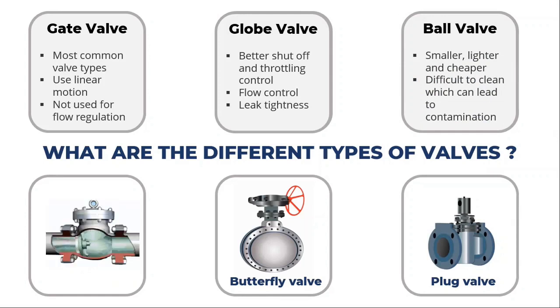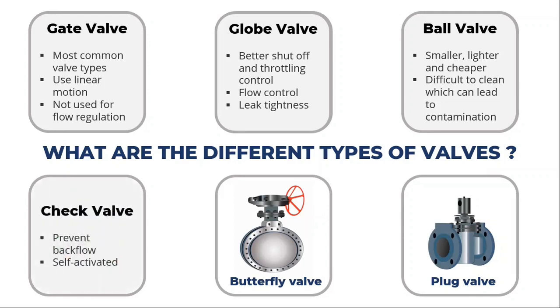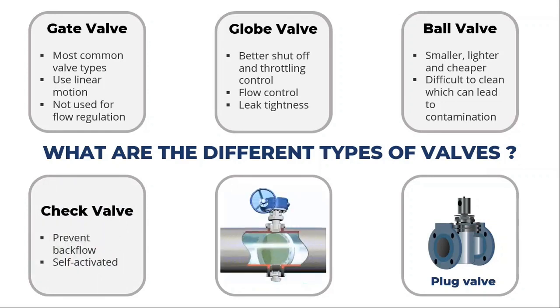Ball valves are challenging to clean, which might result in contamination, and they are not appropriate for applications that need constant throttle control. A check valve is used to stop backflow. These valves are normally self-activated, opening when media flows through the valve in the desired direction and closing when flow reverses.